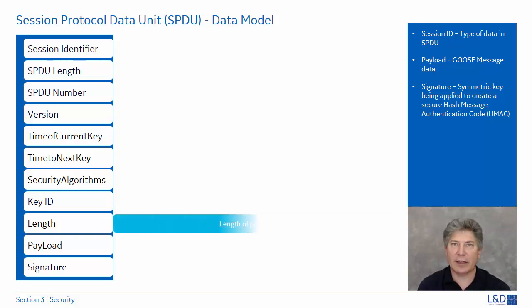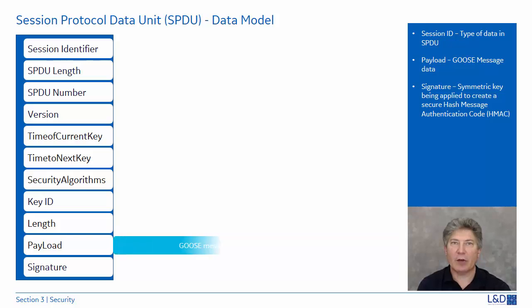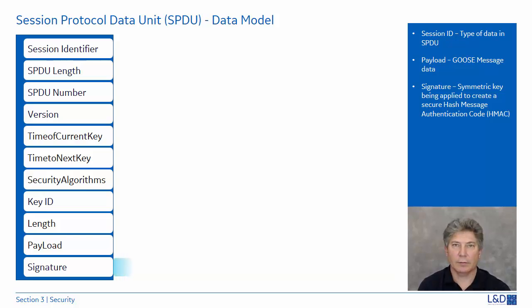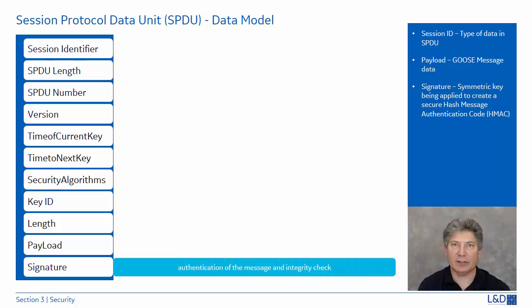The length field is the length of the payload data. The payload is the GOOSE message, including the simulation bit, the application ID, and so on. And finally, the signature — this is a secure HMAC, or Hash Message Authentication Code, which is like a CRC, a cyclic redundancy check, used for authentication and integrity checks.